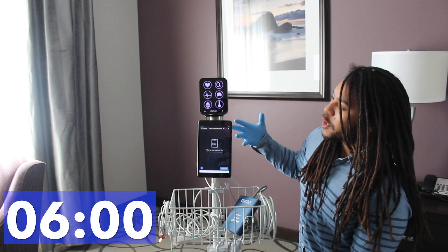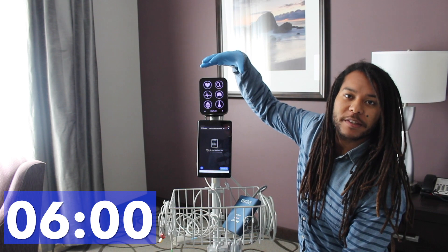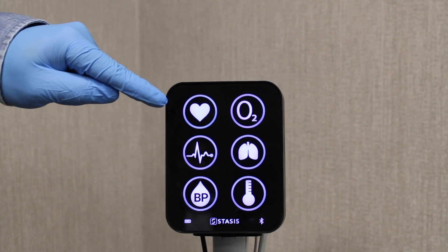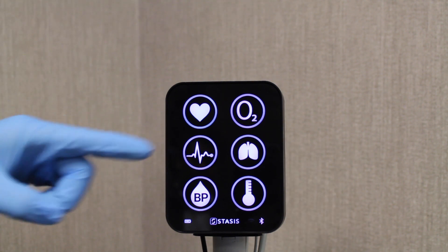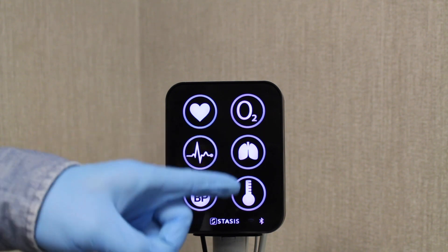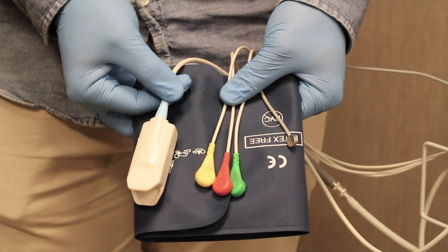So here we have our finished kit. We have the six parameter monitor ready to be deployed at the bedside to measure the patient's vitals. This monitor measures heart rate, blood oxygen, electrocardiogram, respiratory rate, blood pressure, and temperature. And it measures the vital signs using standard hospital probes.